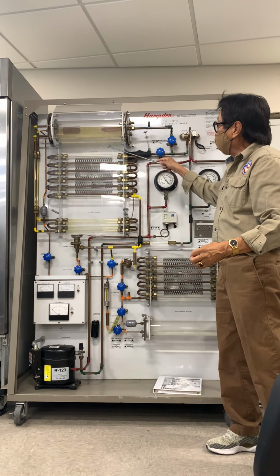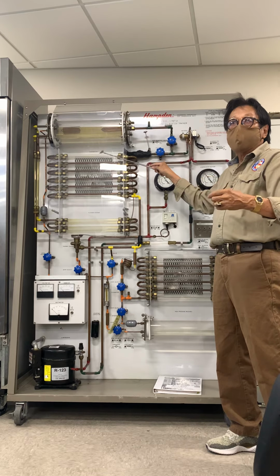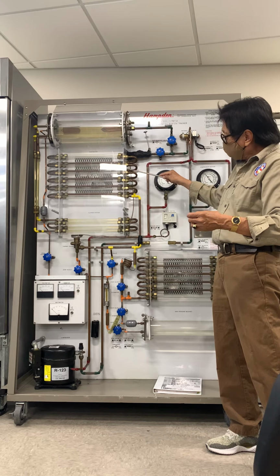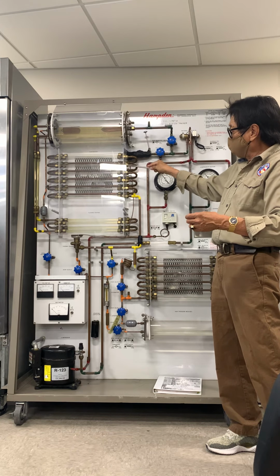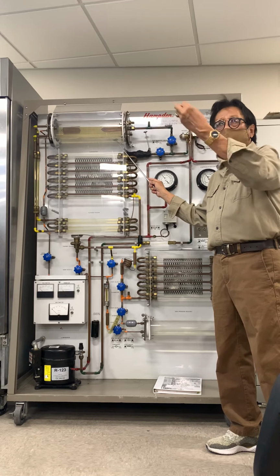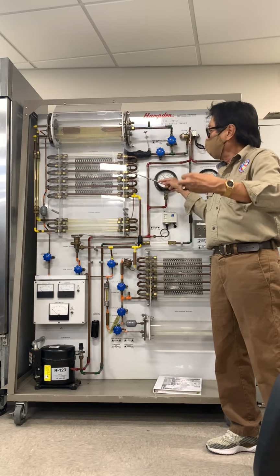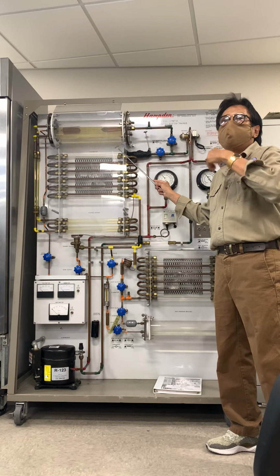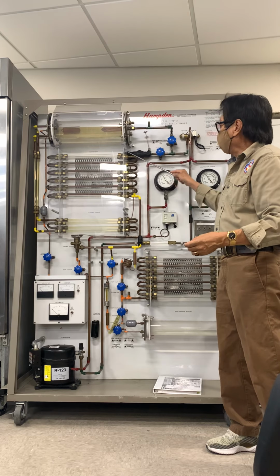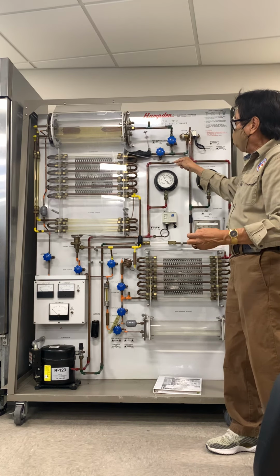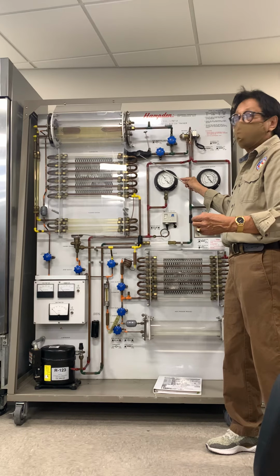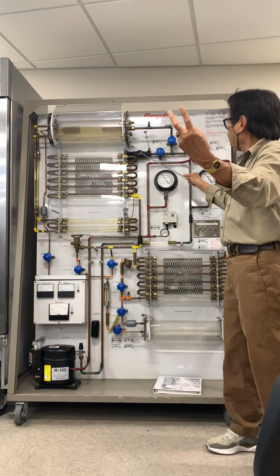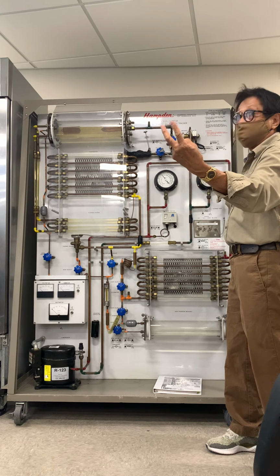But it would still have a few tubes to travel before it completely exits the evaporator. As the gas travels through the remaining tubes, it continues to absorb heat circulating from this air over here, and that is when you call it superheated vapor. It would exit the evaporator as a superheated gas or superheated vapor, both still low pressure and low temperature. It would exit and pass through this valve.